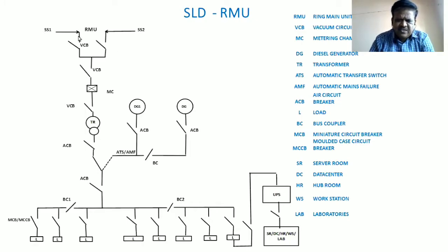To avoid this, they use interlocking switches in these breakers, so that when this is switched on, you cannot switch on the other. If you try to switch on, it never connects unless you switch off this one, because the NC of this is connected in series with this, so only when you switch off can you operate this. These are called interlocking switches.